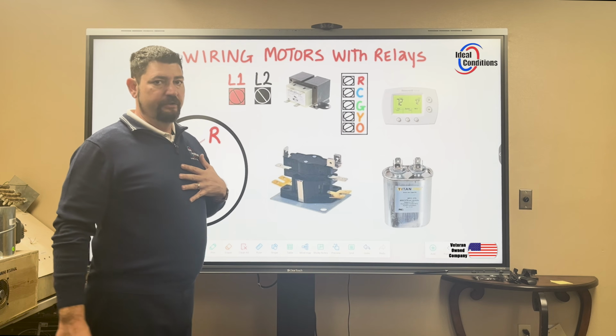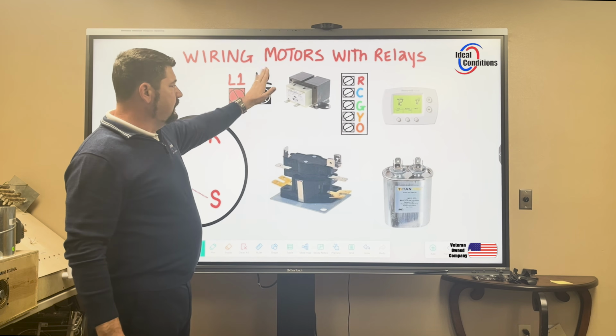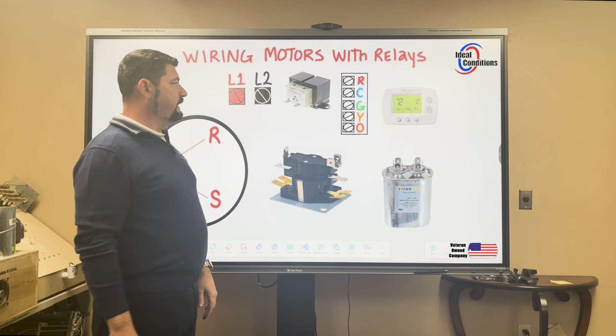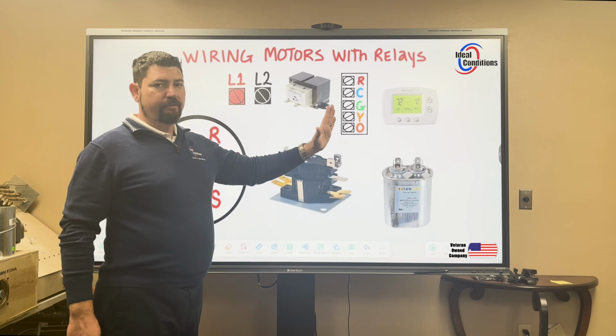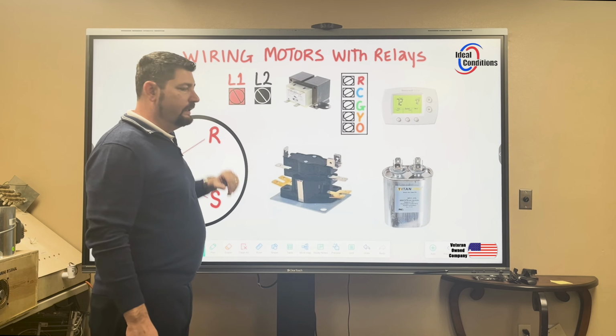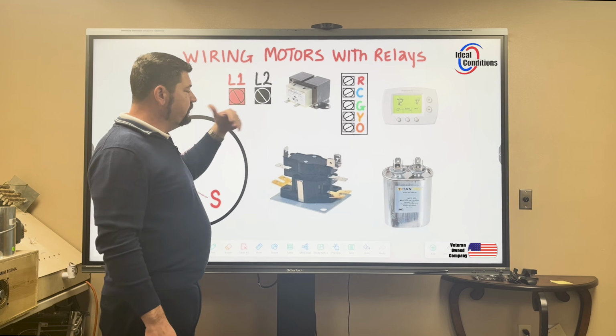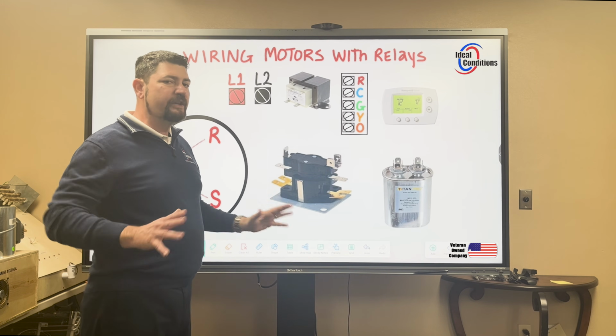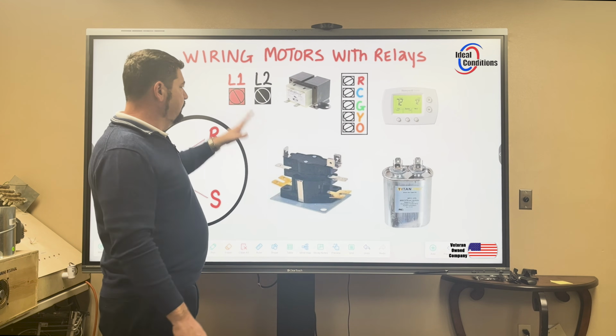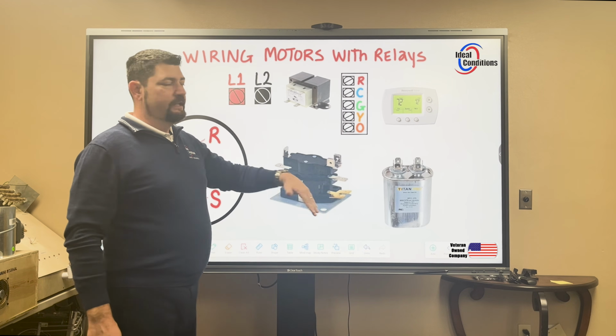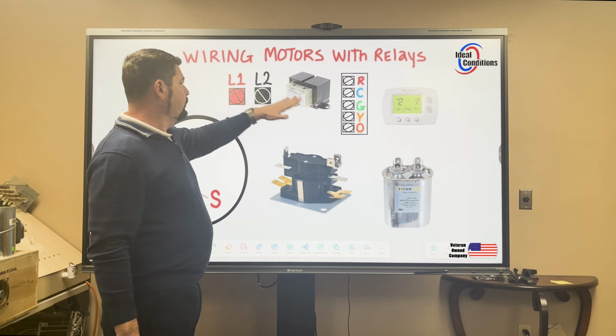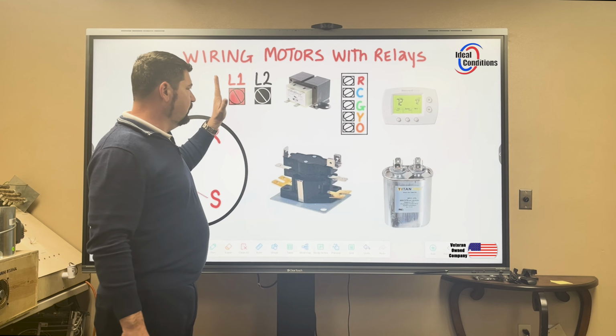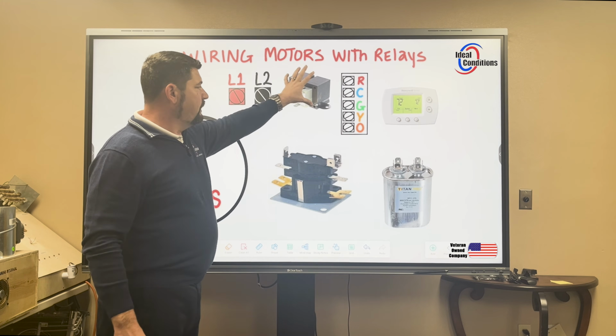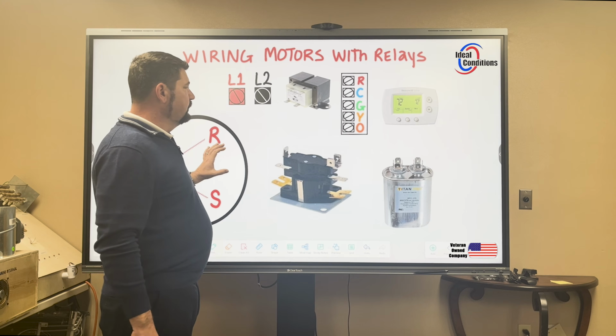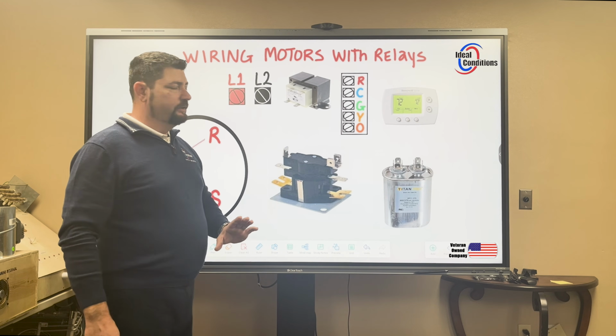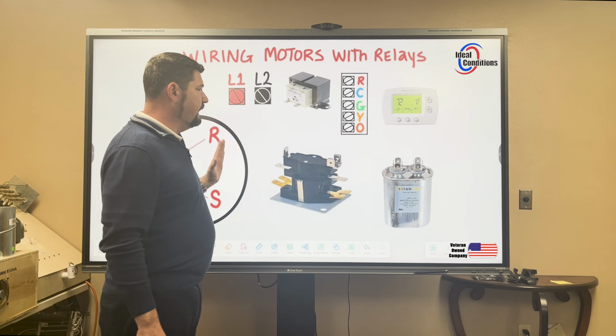So my tip for you is start with one leg, the high voltage side, complete it all the way through. Then go to your next leg, complete it all the way through. As you do these, inspect to make sure nothing's questionable. Then when you're done, work on the low voltage. Never work on one leg, then low voltage, then back to the other leg. You don't want to go one component at a time — that's not good practice. You want to go one leg at a time.